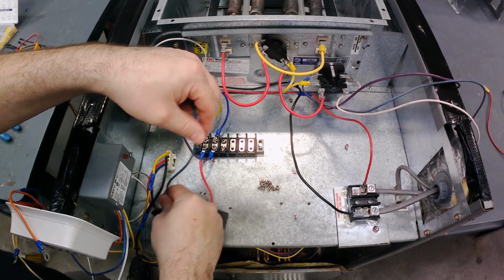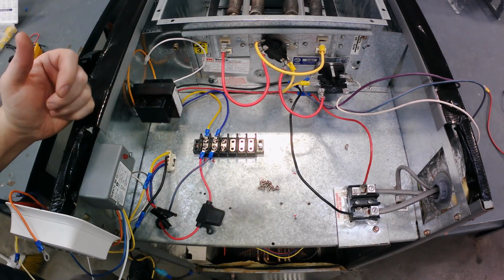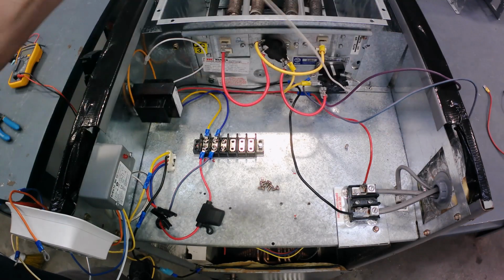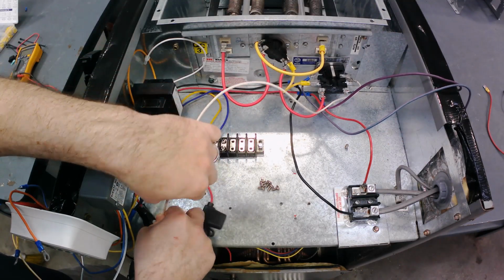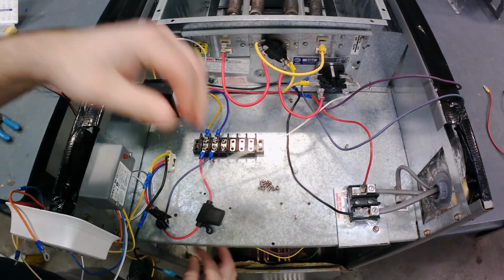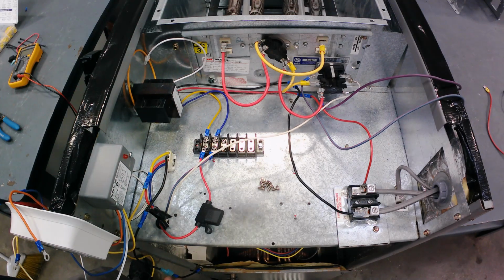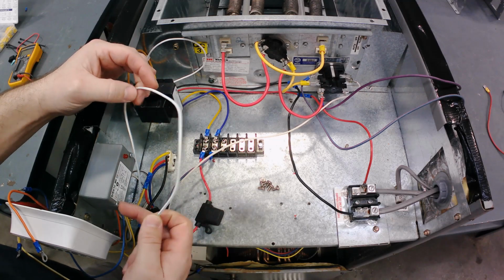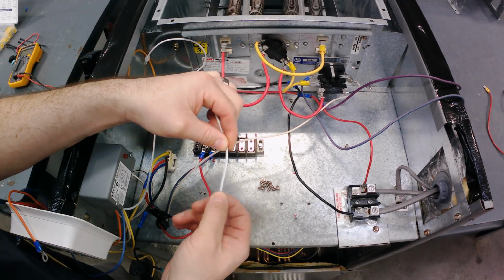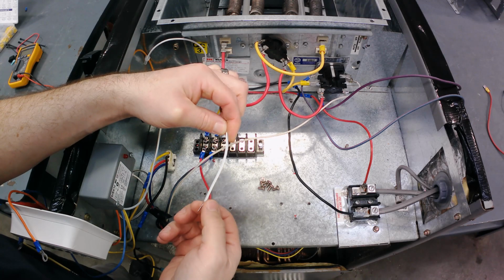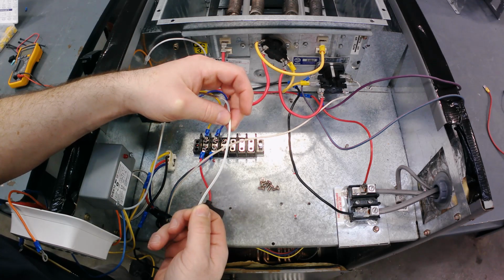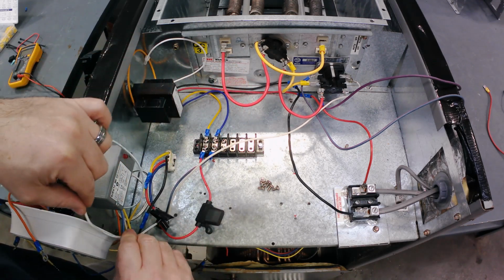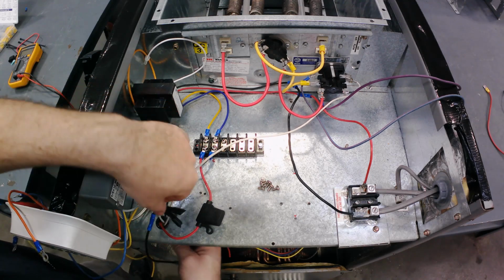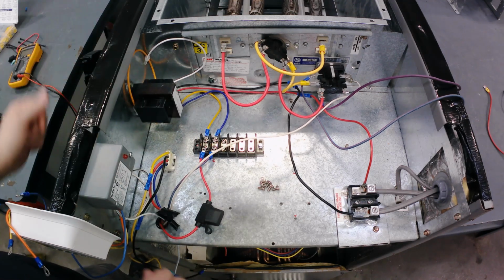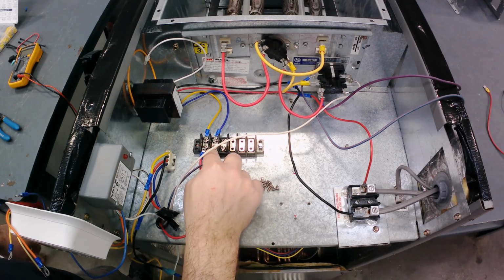We're going to tuck that down here so we can do the low voltage. I'm also going to pull the white down here to do the low voltage for that. For the indoor fan, I'm going to pull off this RIB relay. The blue with the yellow stripe is the connection for our 10 to 30 volt AC or DC, so I'm going to pull that down. The white and yellow is going to be a common, so we'll leave that one up here and terminate it over here with this common as well.